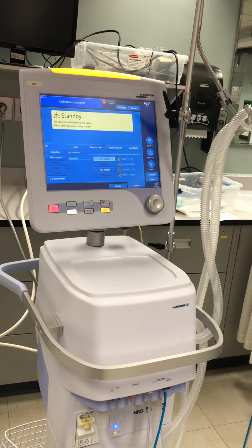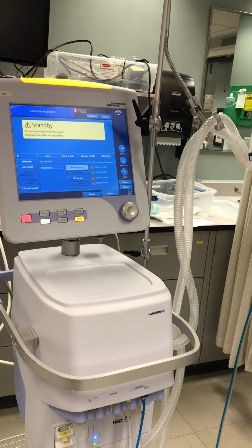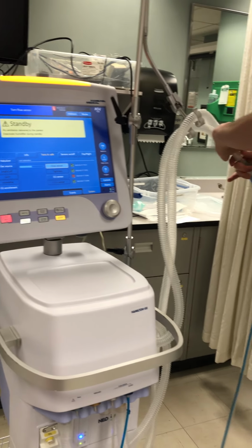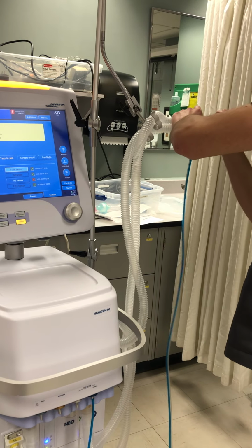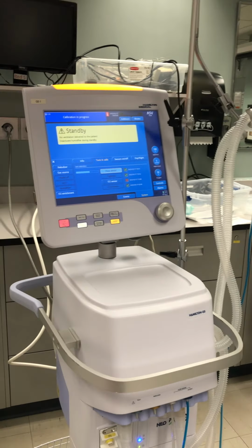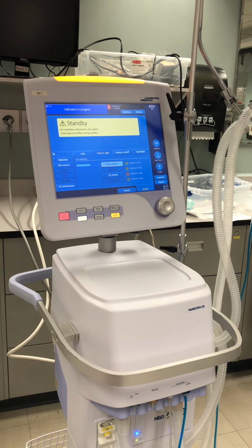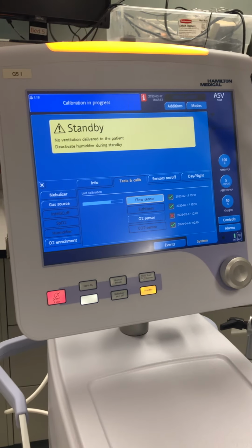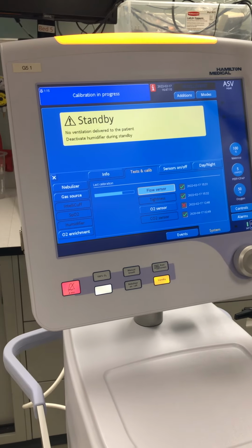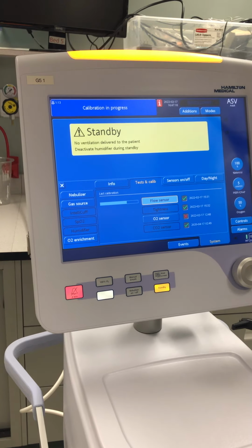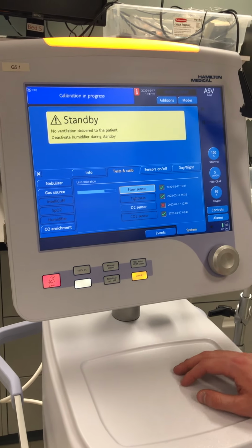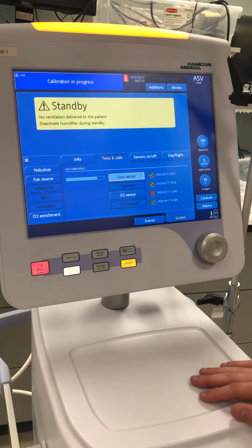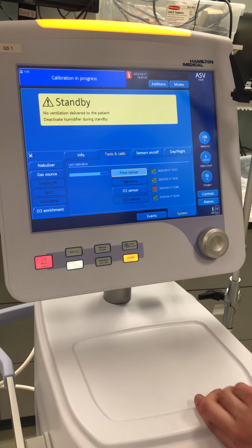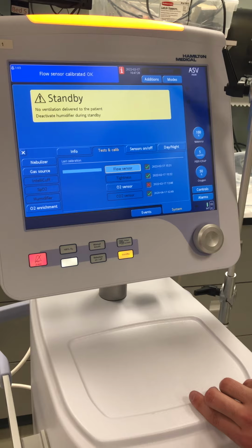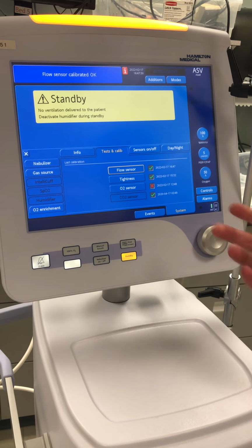Yep, overall a fairly simple procedure. If you want, you can skip a minute into the video. It'll ask you to turn it again, so you unplug, you turn it again. Calibration in progress, once again. So just make sure when you're setting it up, read over here, do whatever it tells you. With this ventilator, if you don't follow the instructions fast enough, it can actually fail certain tests. So when it says turn flow sensor, you turn it relatively quickly, or it will just fail.